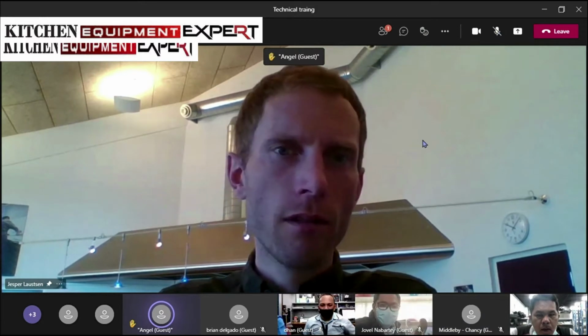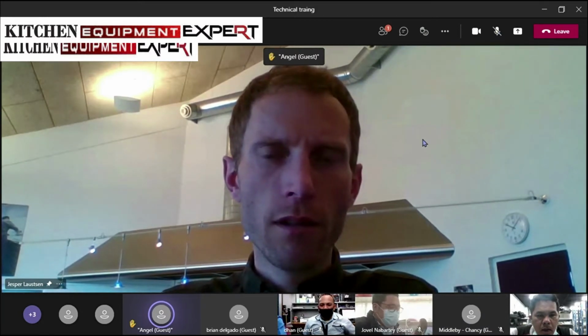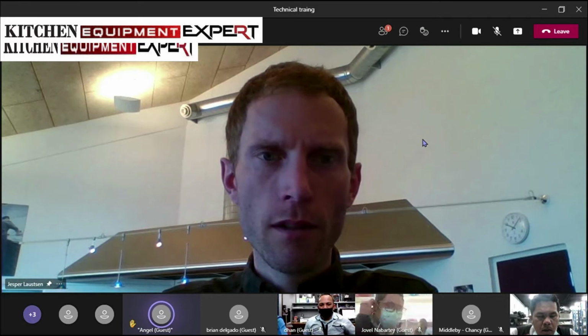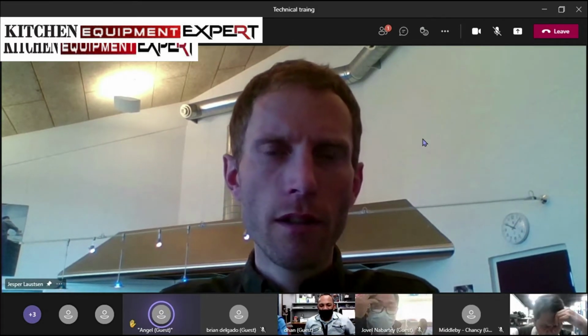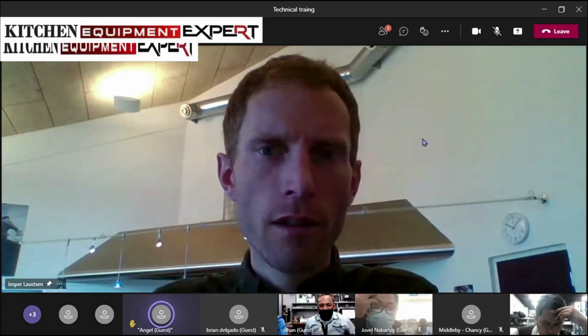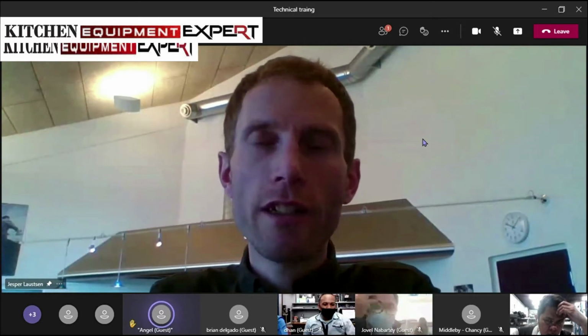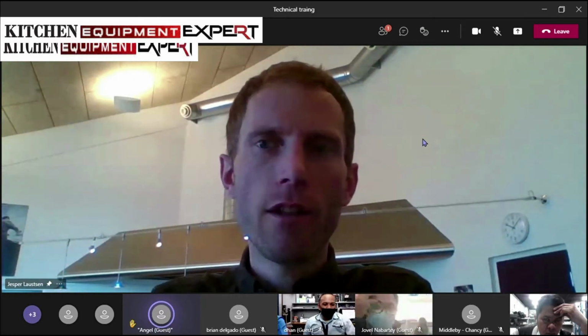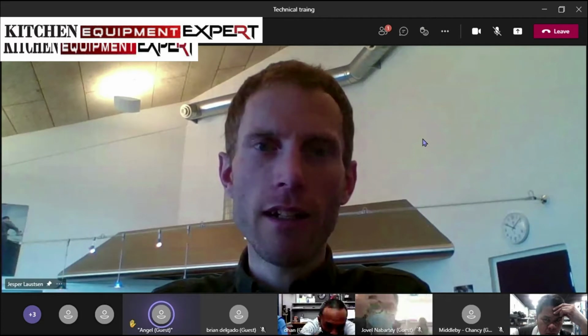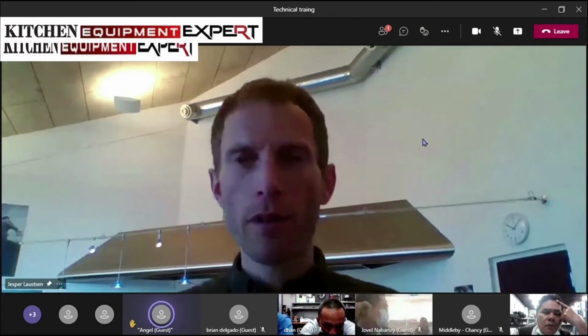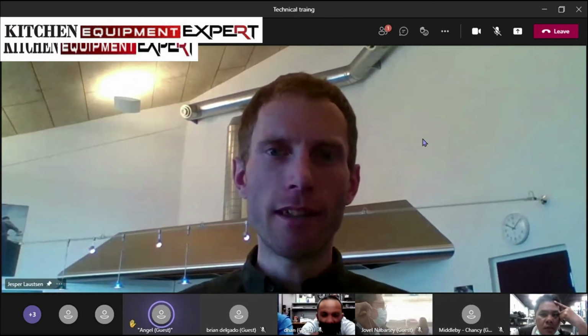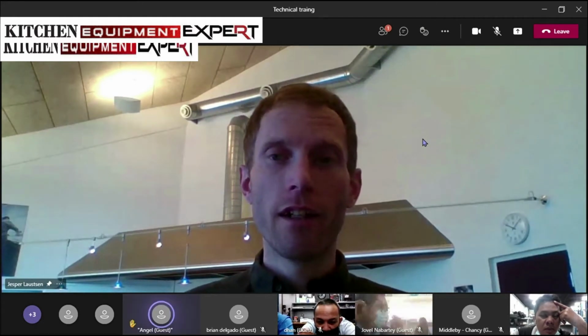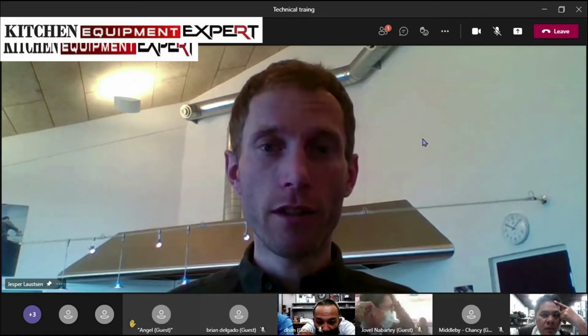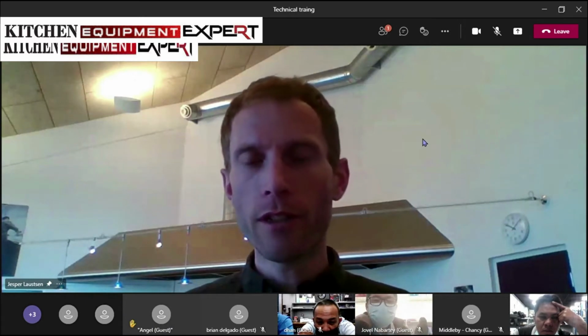Yes, Angel? Hi sir, what Sir Chancy means is, what if the unit exhaust on top is blocked? What could possibly happen? If the exhaust is blocked, the part that has blocked the exhaust pipe can start a fire, because the exhaust temperature is very high, up to 600 degrees.